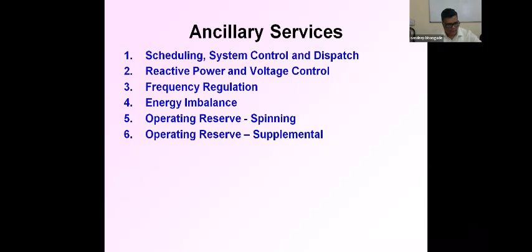Frequency regulation is the minute-to-minute adaptation of the generator output to meet the imbalance between total supply and demand in the system. Now, this instantaneous response of the generating unit is usually achievable through the use of governor droop characteristics, okay, or an automatic control signal from the control area based on determining the required change up or down in the real power output to bring the area control error within bounds, area control error.